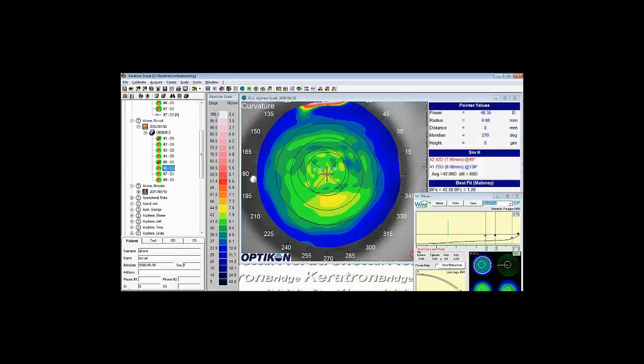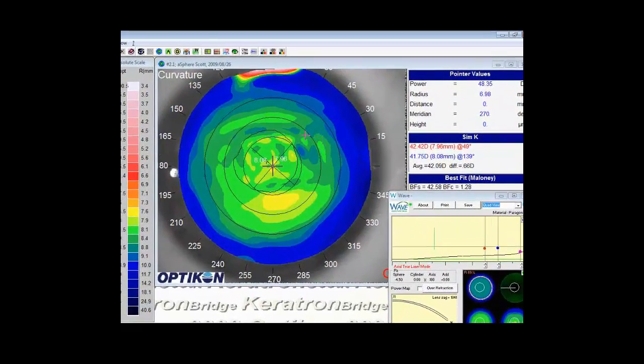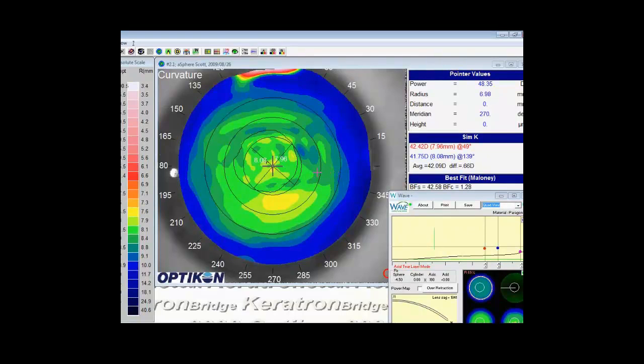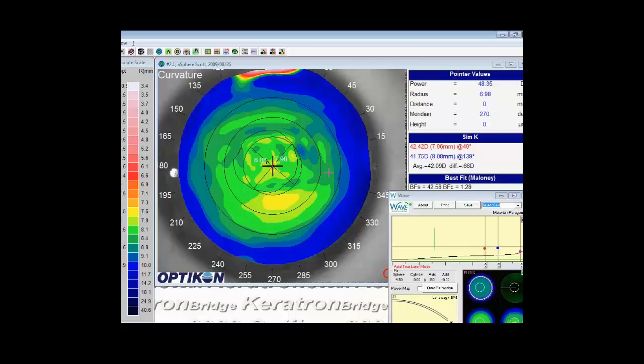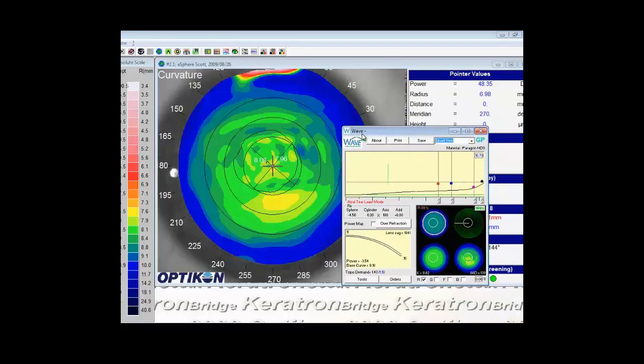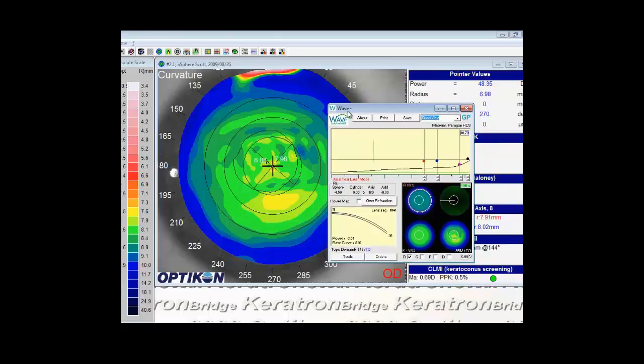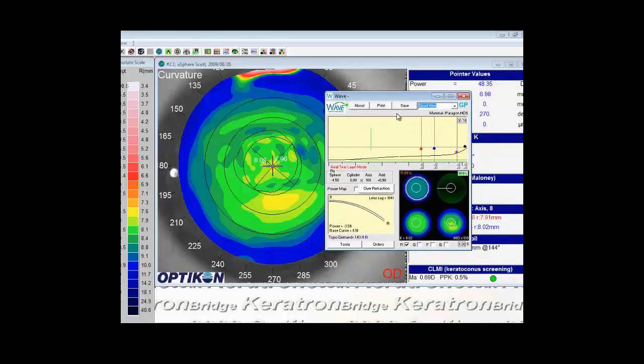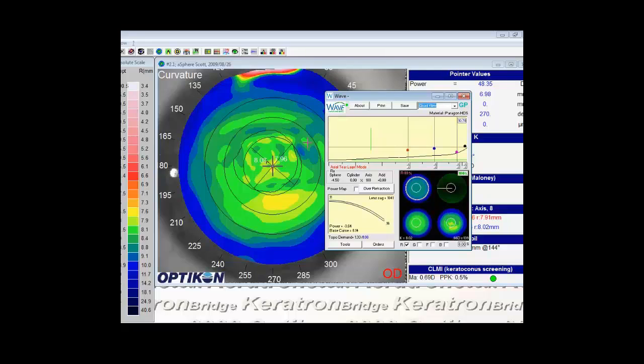If we look at this topography again, I always keep these rings up. This ring is a 3 millimeter ring, a 5 millimeter ring, and a 7 millimeter ring. It gives me a good reference point on where this peripheral cornea flattening begins. You'll find on most corneas it's right around the 6 millimeter area, right in between this 5 and 7 millimeter. I'm looking at where the general shape of the cornea coloring of the curvature map goes from green to blue, and that's right in this region. Once I've entered the appropriate diameter, I will move this in to a 6-0 based upon this value here.